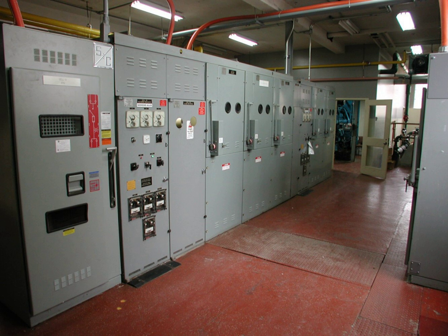Layout details and construction of electrical rooms will be controlled by local building code and electrical code regulations. Requirements for an electrical room relate to fire safety and electrical hazards. An electrical room is usually required to be secured from access by unauthorized persons. These rules are especially strict where equipment within the room has exposed live terminals. Regulations may require two separate means of exit from a room where the power rating of circuits exceeds some threshold, to allow for quick exit in an emergency.